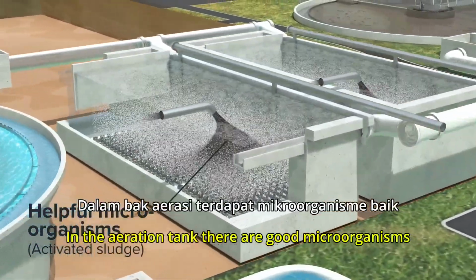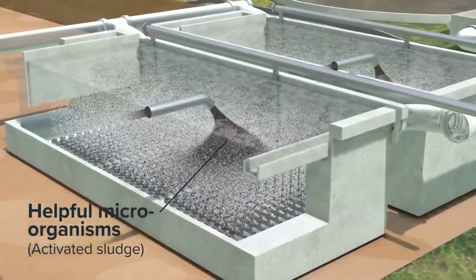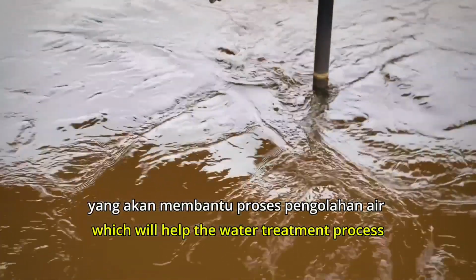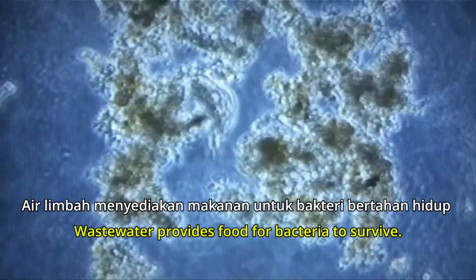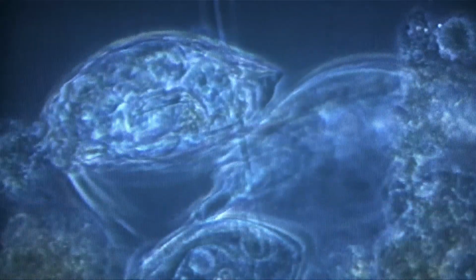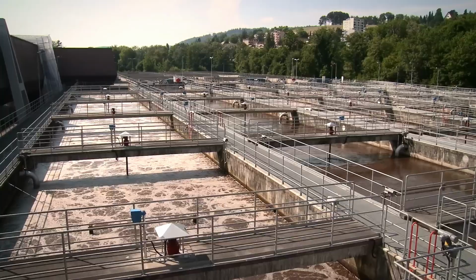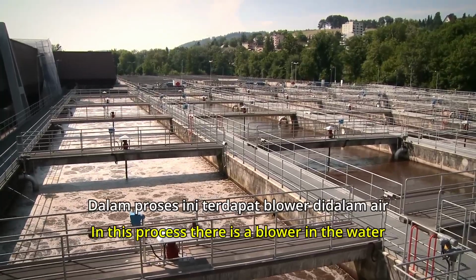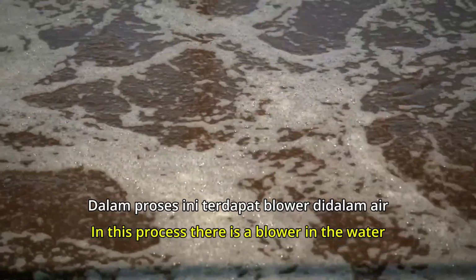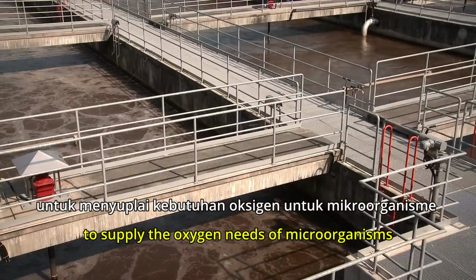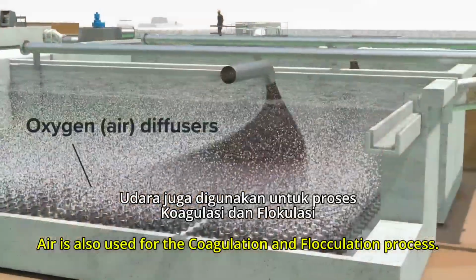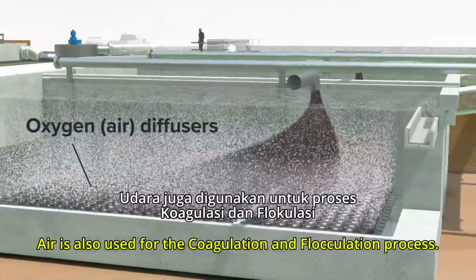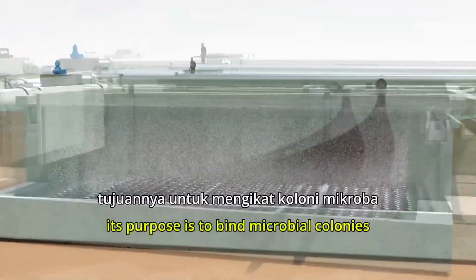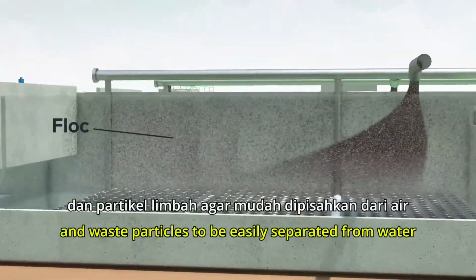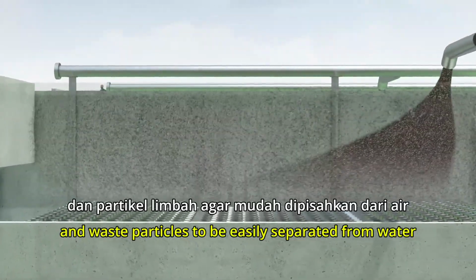In the aeration tank there are good microorganisms, which will help the water treatment process. Wastewater provides food for bacteria to survive and digest waste naturally. In this process there is a blower in the water to supply the oxygen needs of microorganisms. Air is also used for the coagulation and flocculation process. Its purpose is to bind microbial colonies and waste particles to be easily separated from water.